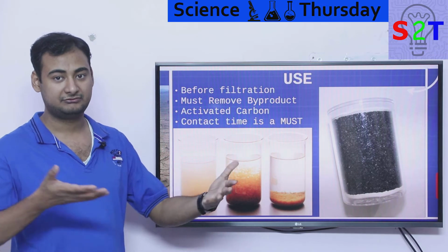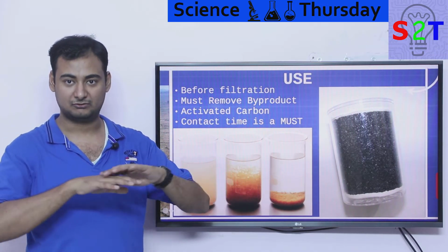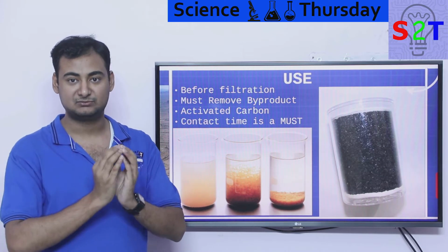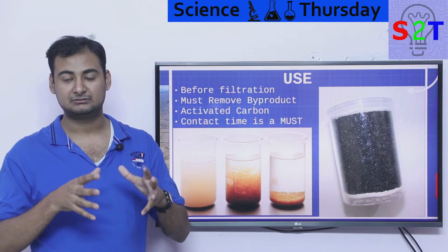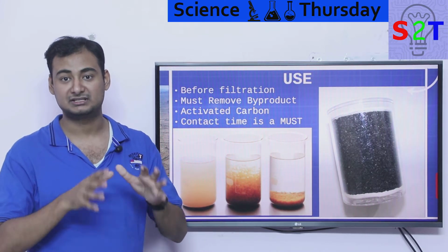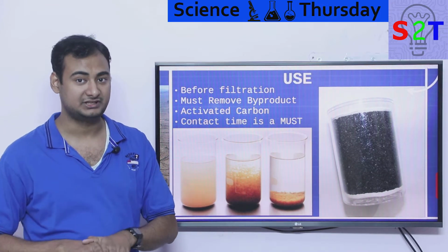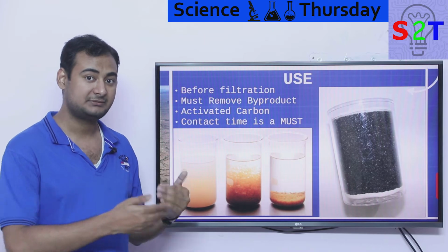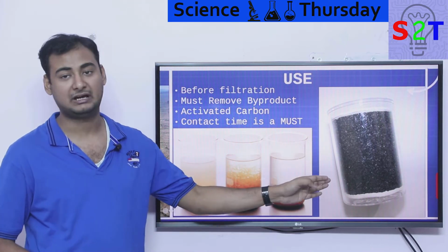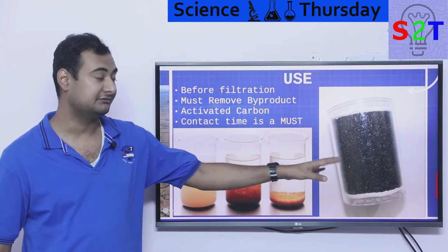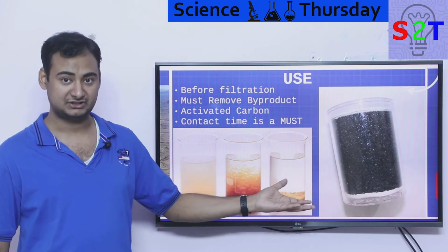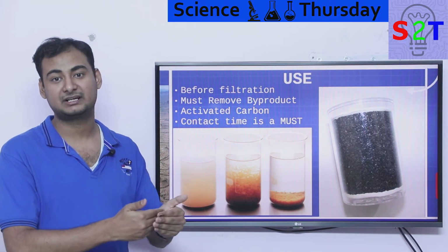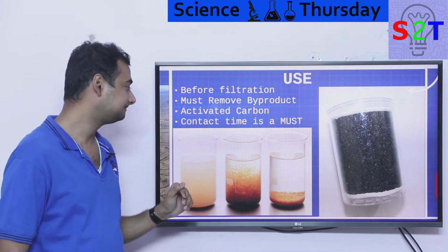Basically if you have a filter, a heavy pond of water or for water treatment, and you put ozone into it, it will help small ions become big stable ions. Basically it will become heavier salts that will allow them to sediment much more easily. So it actually helps in another process. That's why people want to do ozone before it goes into activated carbon. This will help activated carbon to remove much more efficiently. So it's not something you do at the last. UV is something you do at last, this is something you do at first.